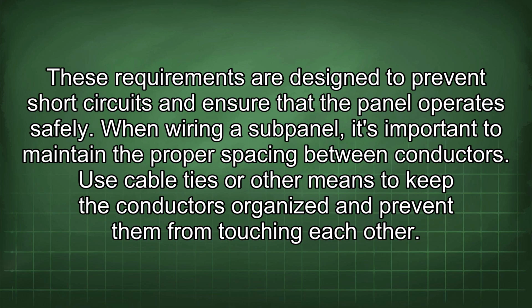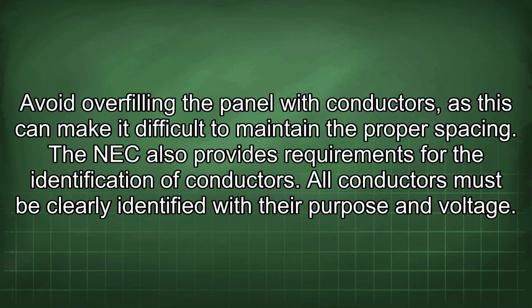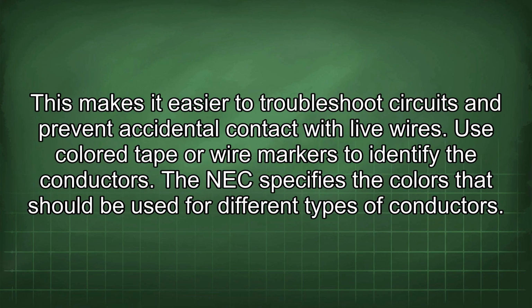When wiring a subpanel, it's important to maintain the proper spacing between conductors. Use cable ties or other means to keep the conductors organized and prevent them from touching each other. Avoid overfilling the panel with conductors, as this can make it difficult to maintain the proper spacing. The NEC also provides requirements for the identification of conductors. All conductors must be clearly identified with their purpose and voltage. This makes it easier to troubleshoot circuits and prevent accidental contact with live wires.